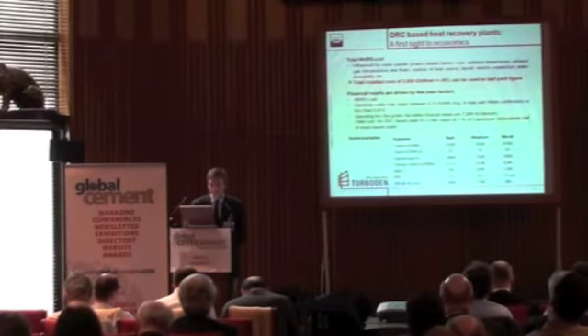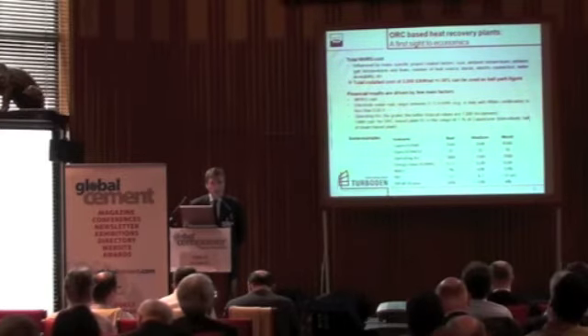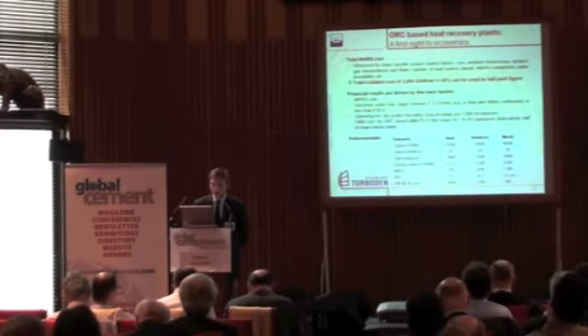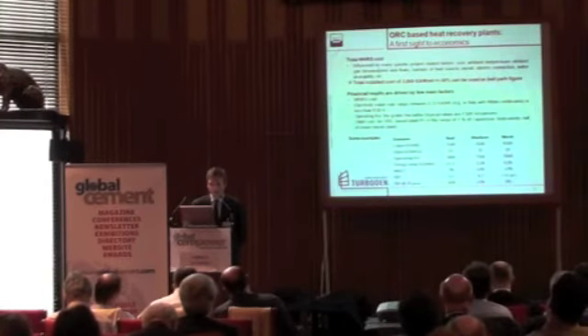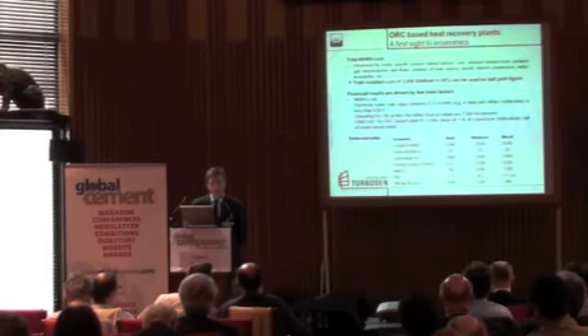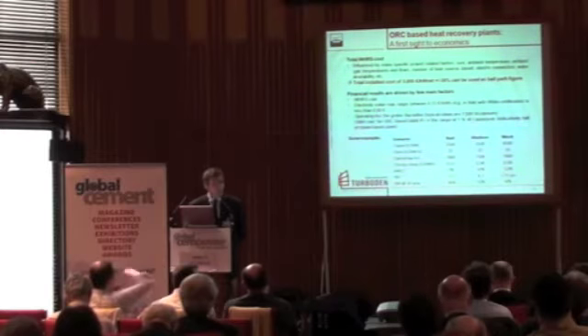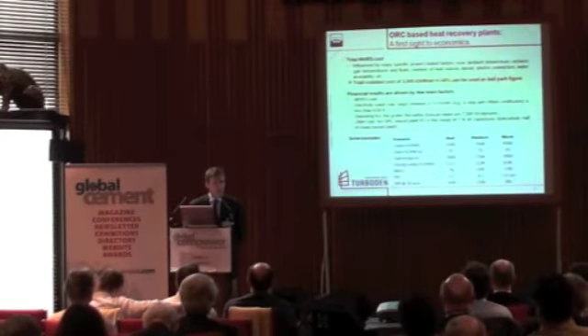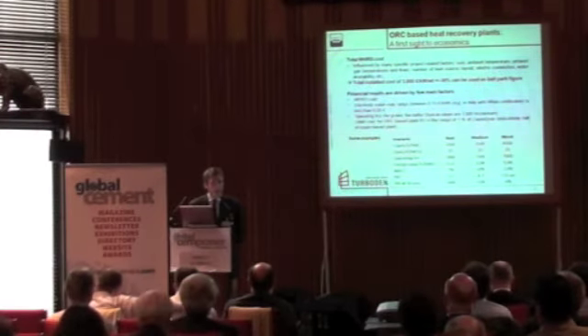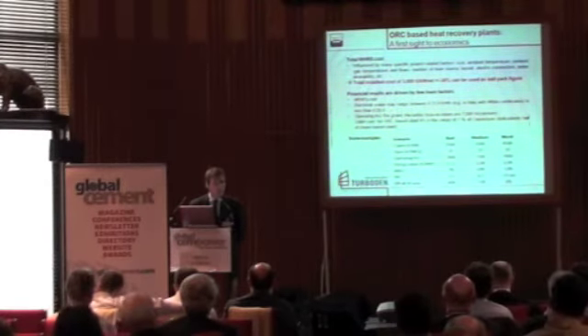If you go through the numbers, you see at the very bottom that the payback times that can be expected for such a recovery system are in the range of 3 years in the very best case, which is maybe unrealistic, and up to 8 to 9 years in average market conditions. But even worse, clearly, if you take a very small plant in a very low energy price market, payback will never happen. So this is just to tell you, if you have in mind a 2 year payback, my suggestion is just forget it and change the target to maybe 5 years, which is quite more realistic.